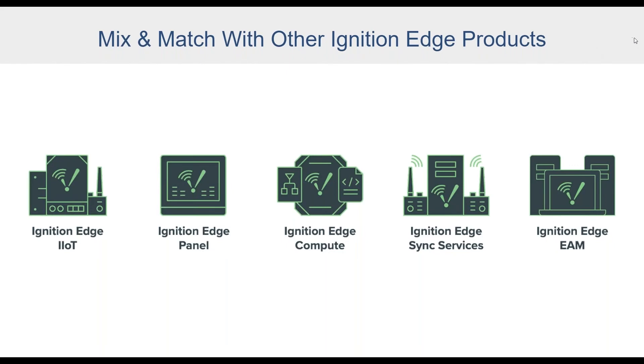This centralized management is a truly differentiating feature of Ignition as an HMI solution. Say a panel goes down and needs to be replaced — you grab whatever hardware is available, install Ignition, and connect it to the central Ignition Edge EAM. Via EAM, it already has the backups it's been taking, so it can restore the right backup to that panel, all centrally. Your floor staff just have to plug it in and make sure it's connected — EAM does the rest. Really powerful.